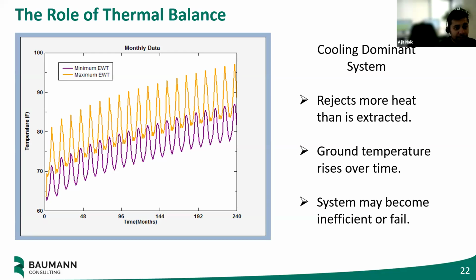Typically you run a 20 or 30 year simulation. Here, by year 20, the maximum temperature coming out of the loop starts approaching 100 degrees. Many heat pumps have a maximum operating limit of 90 to 95 degrees, so once you get to 100 or 110 degree water, forget about boiling concerns, you might just be out of luck. The heat pump won't provide cooling with 110 degree water. Worst case, these systems can outright fail, or even before that, they get really inefficient because you're right at the limit of the heat pump, and it won't operate well.